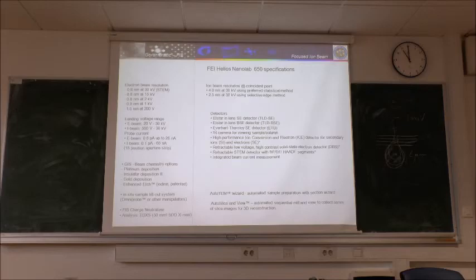There is also some special software like AutoTEM. So you just press the button and in 1 or 2 hours it will make a lamella completely automatically. In reality, it means that after 5 minutes it stopped working because there's some problem, something corrupted, and so on. Of course, if you do this on a uniform, ideal sample like the surface of silicon, it could be done. But if you're using a practical sample with a lot of pores and other features, then this automatic recognition system somehow fails. You have to do it manually, but no problem.